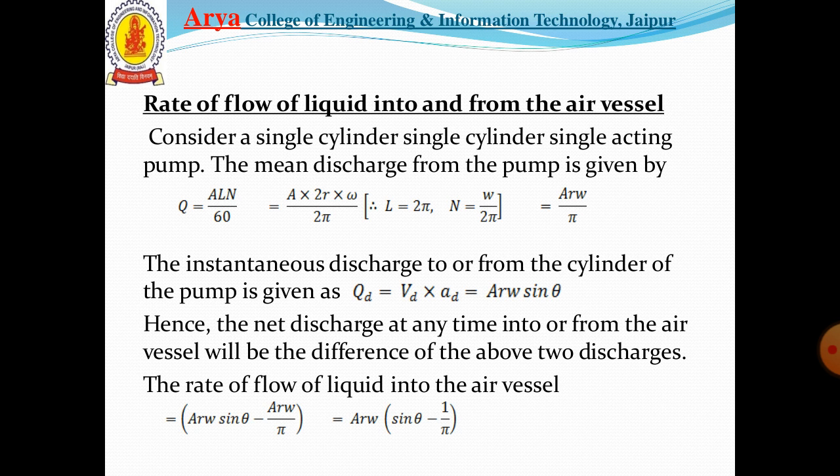Now the calculation for air vessels: the rate of flow of liquid into and from the air vessels. Consider a single acting reciprocating pump. The mean discharge from the pump is given by Q = ALN/60. This can also be written as A·2r·ω/2π, where r is the radius of the crank and ω = 2πN/60. The instantaneous discharge is qd = A·r·ω·sin(θ). The rate of flow of liquid into the air vessel equals A·r·ω·sin(θ) minus A·r·ω/π, which simplifies to A·r·ω·(sin(θ) − 1/π).